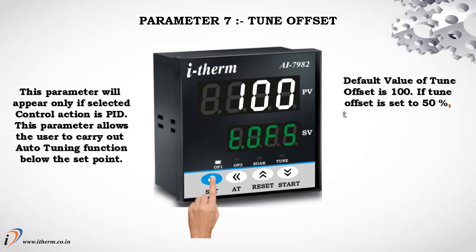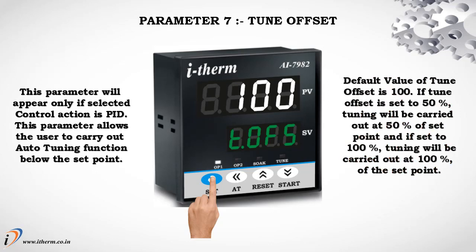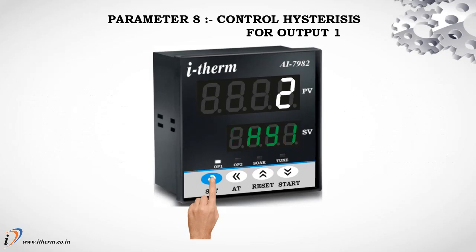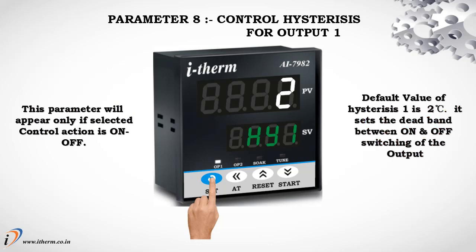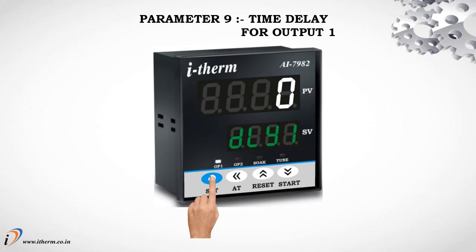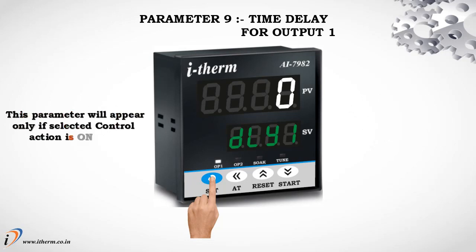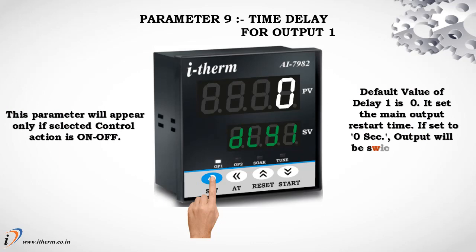Parameter 7: Tune offset. This parameter will appear only if selected control action is PID. This parameter allows the user to carry out auto-tuning function below the set point. Default value of tune offset is 100. If tune offset is set to 50%, tuning will be carried out at 50% of set point; if set to 100%, tuning will be carried out at 100% of the set point. Parameter 8: Control hysteresis for output 1. This parameter will appear only if selected control action is on-off. Default value of hysteresis is 2 degrees centigrade; it sets the dead band between on and off switching of the output. Parameter 9: Time delay for output 1. This parameter will appear only if selected control action is on-off. Default value of delay 1 is 0; it sets the main output restart time. If set to 0 seconds, output will be switched without delay.